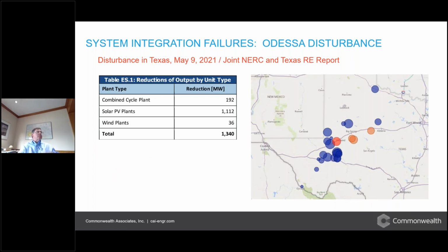Next slide, we move to an incident in Texas, the Odessa disturbance, where over 1,100 megawatts of solar was lost during this disturbance. This was a failed arrestor at a combined cycle plant. You can see in the graphic the red circle is where the fault was, and the orange circles are actually wind.